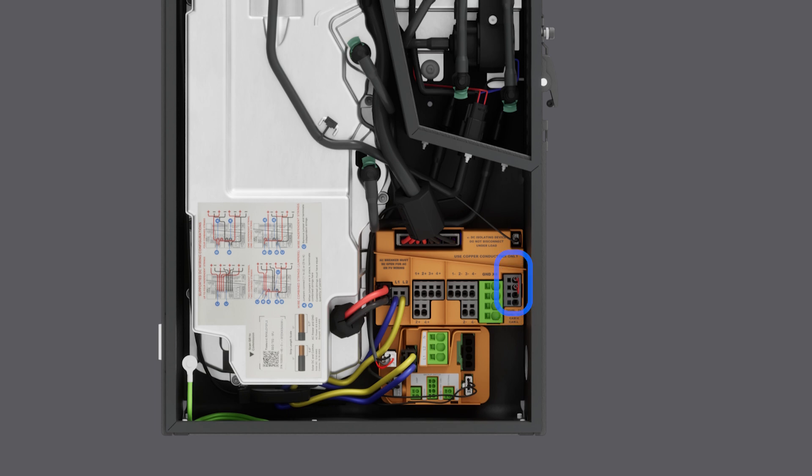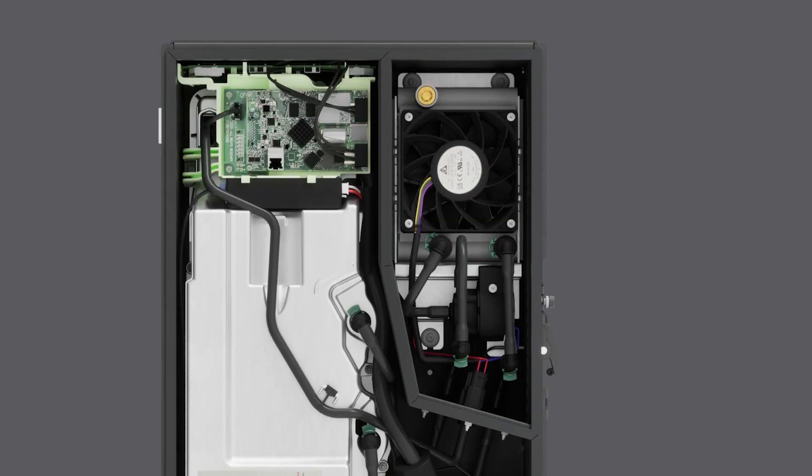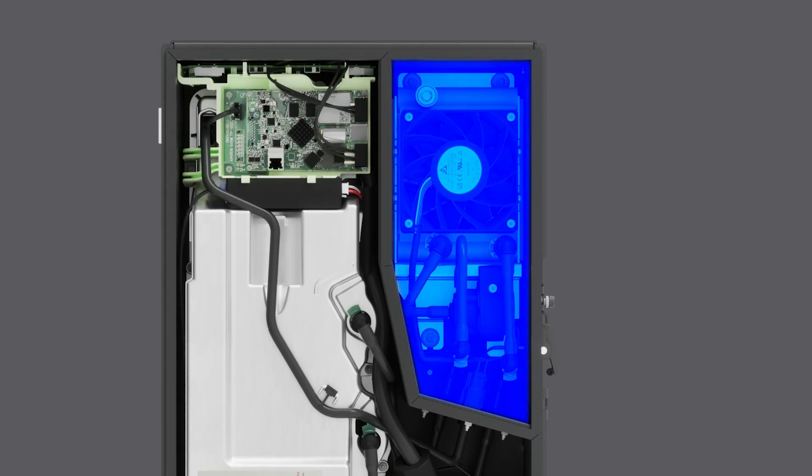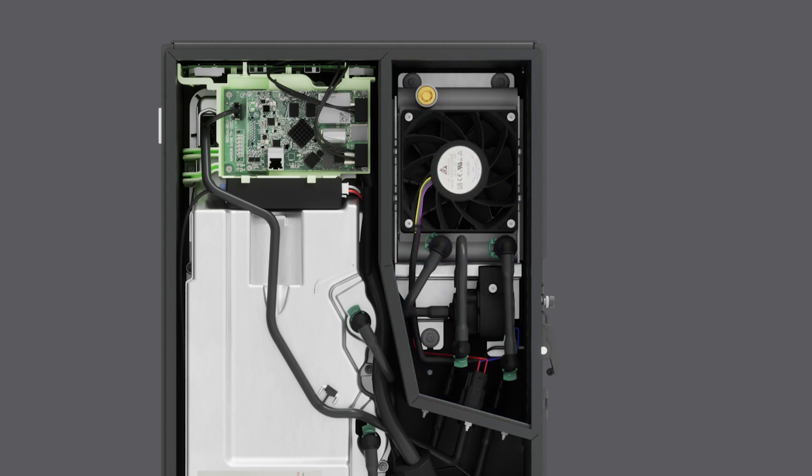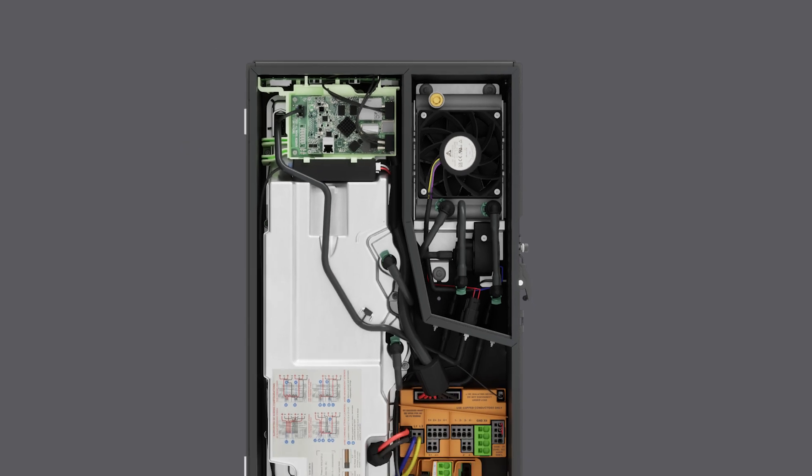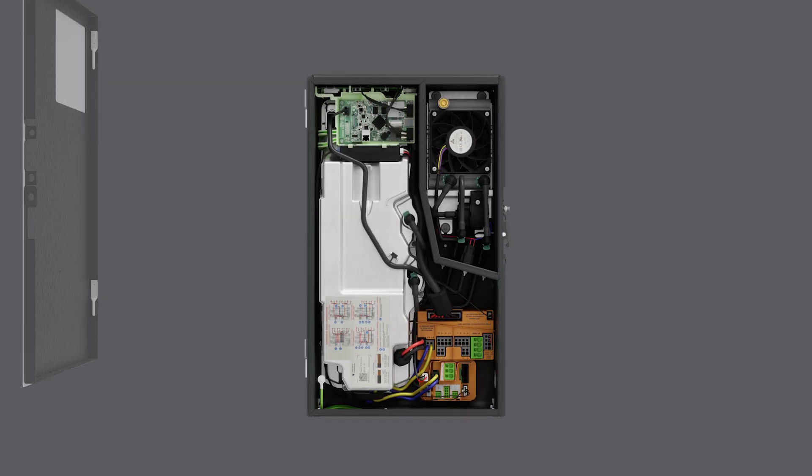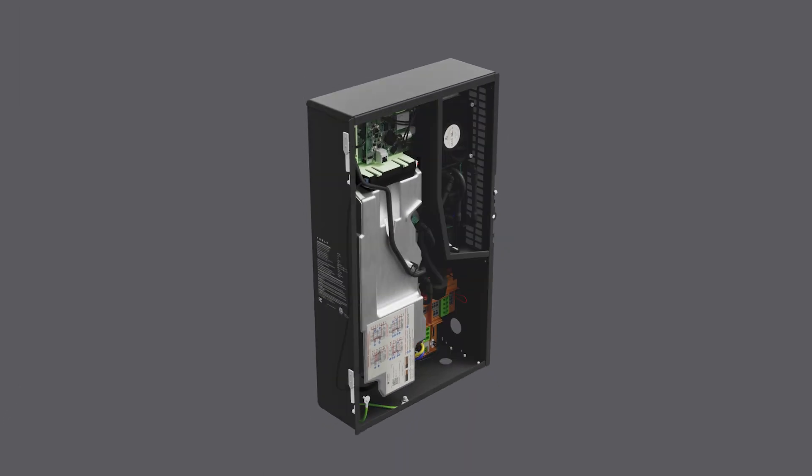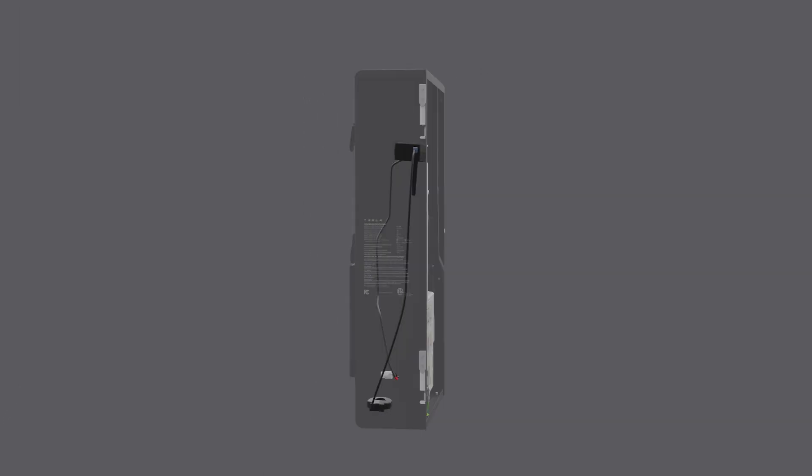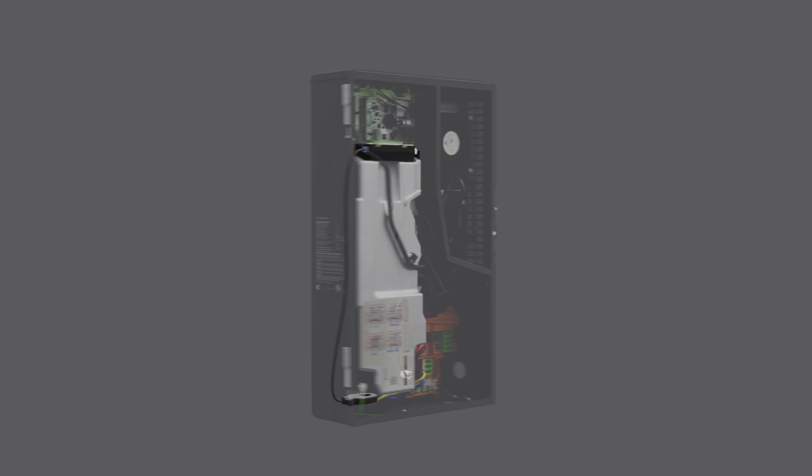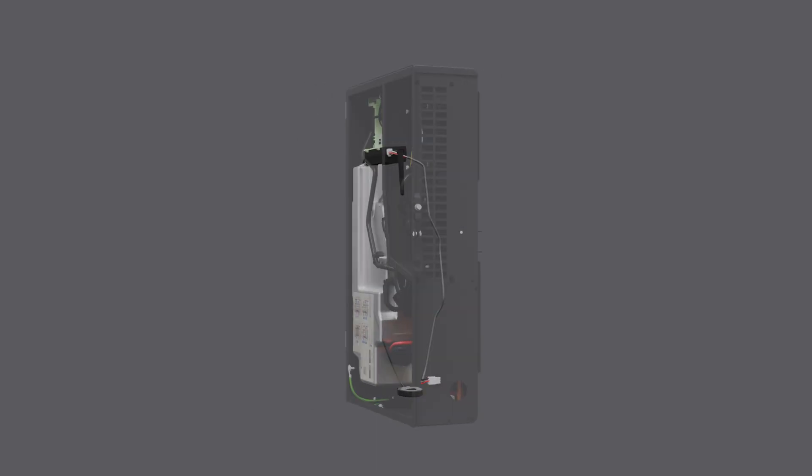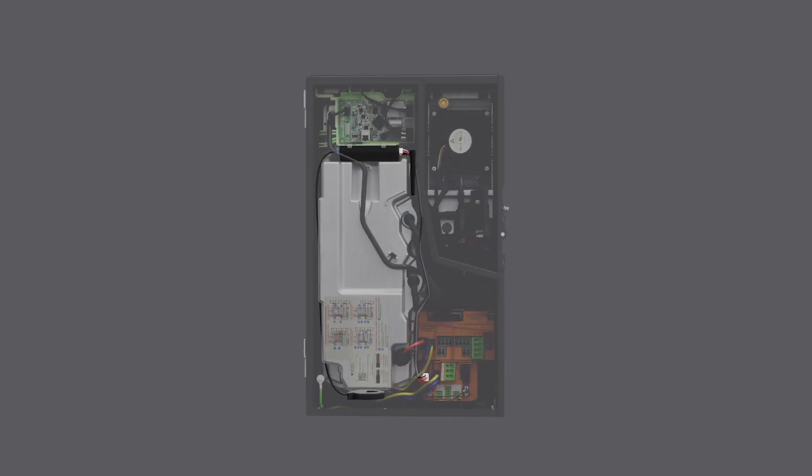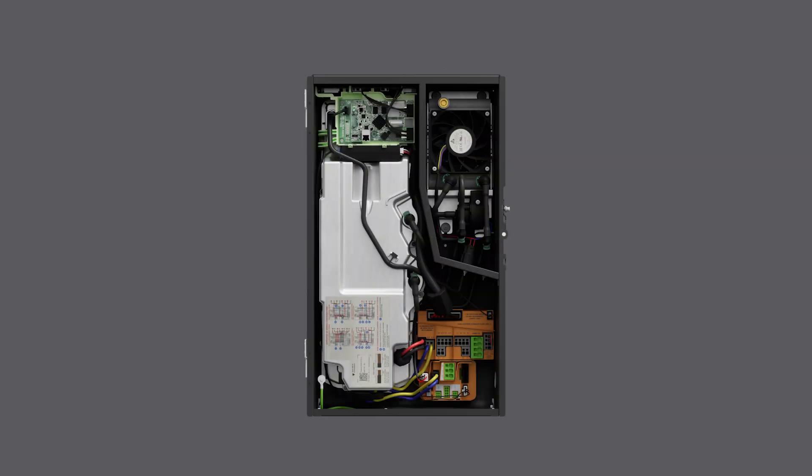At the top right corner of the enclosure is the thermal management system. At the top left of the enclosure is a site controller and factory-installed energy meter. One current transformer is pre-installed to monitor solar production with revenue-grade metering. Three additional current transformer ports are available for monitoring site import and export. For more information about metering, watch the video titled Tesla Solar Inverter Metering.